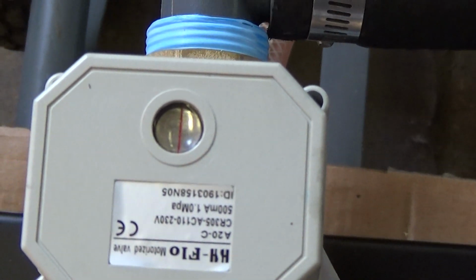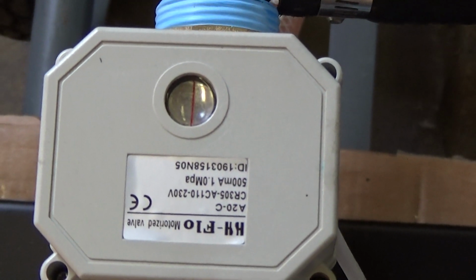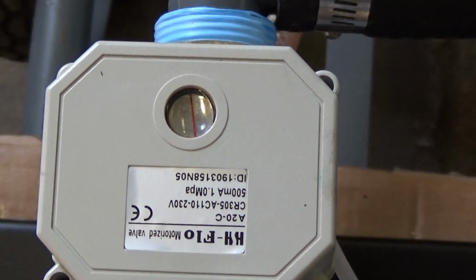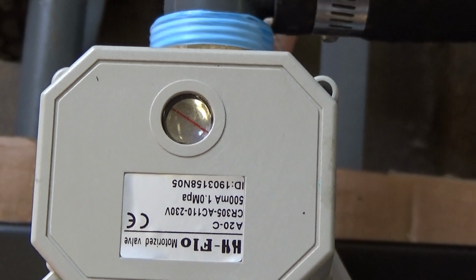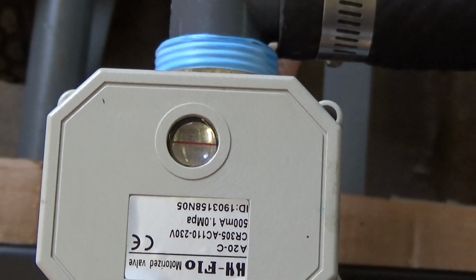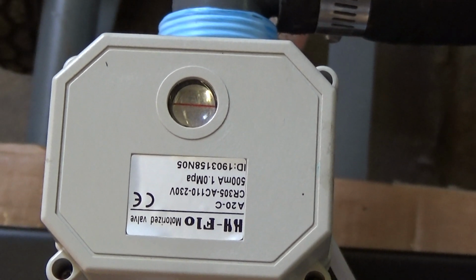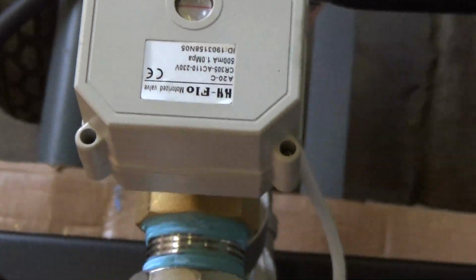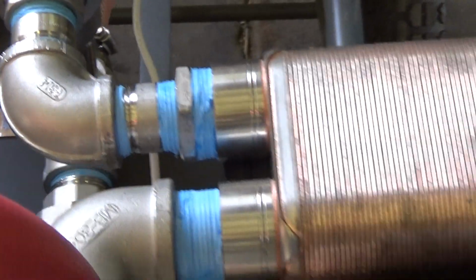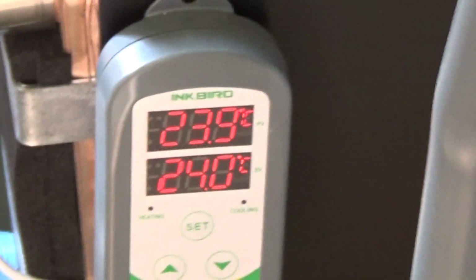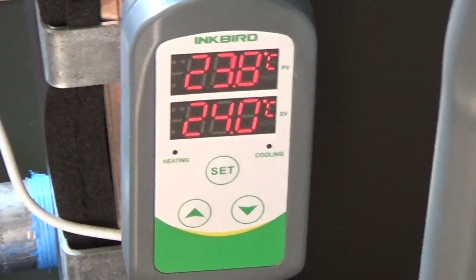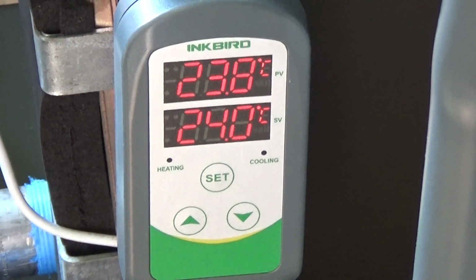Okay, so you should hear the valve as we reach set point. You'll hear a little noise. You'll hear some flow changing too. See, there's the valve closing. And you actually could hear noise that we're now bypassing some of the chilled water flow. Okay, so now on the glycol side, we don't have any chilled fluid going through the heat exchanger.